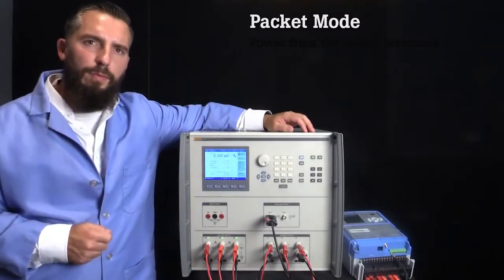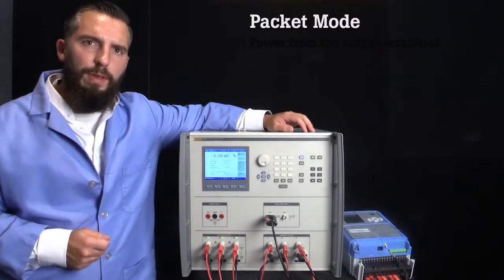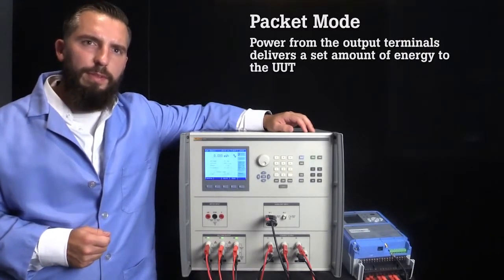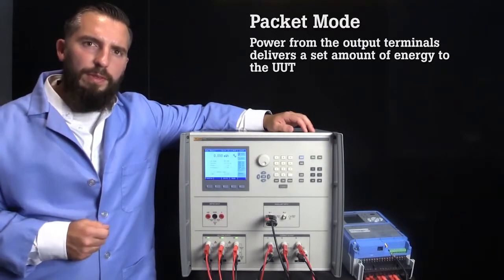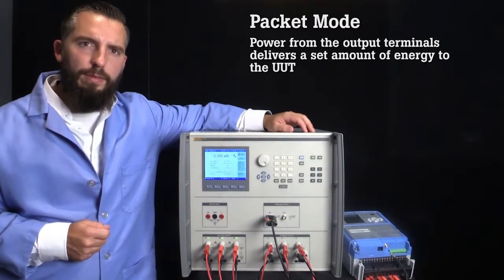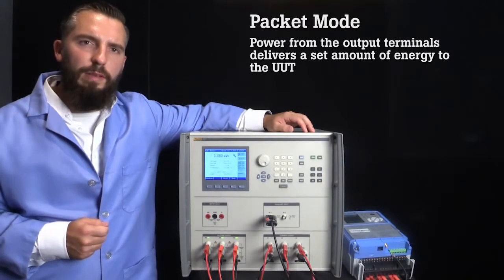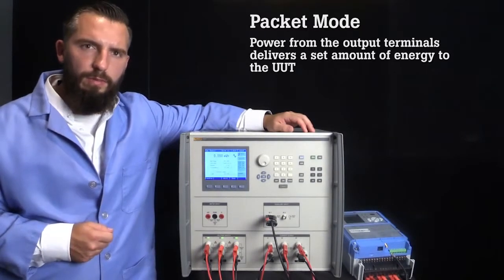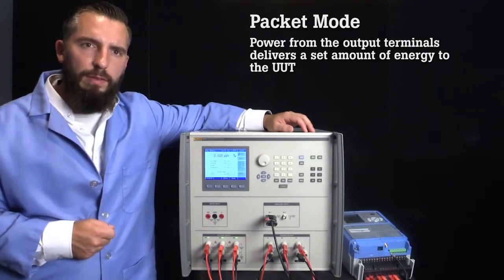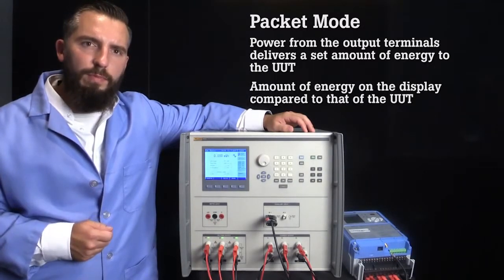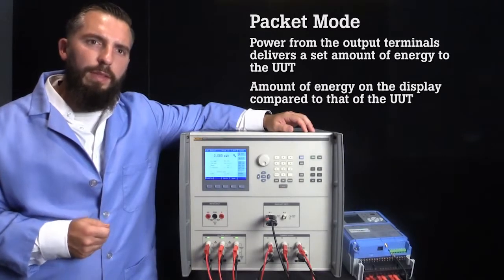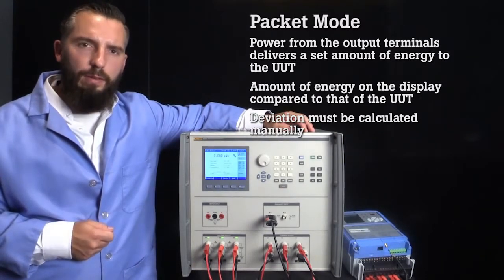In packet mode, which is also known as dose mode, the power from the output terminals is timed to deliver a set amount of energy to the meter under test. This method is not as accurate as the other methods because the start-up time of the 6003A is not synchronized with the UUT, but it is the simplest. To test the accuracy of the meter, the amount of energy shown on the display will be compared to that of the energy meter and the deviation must be manually calculated.